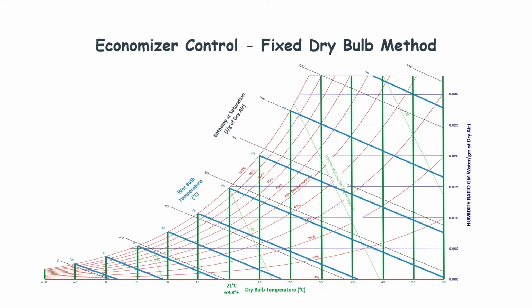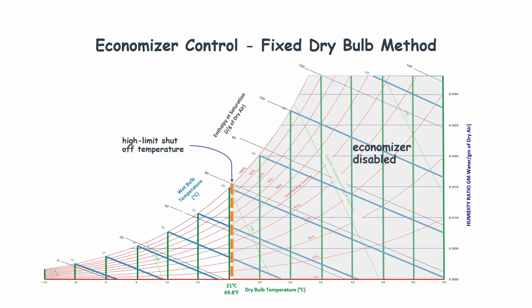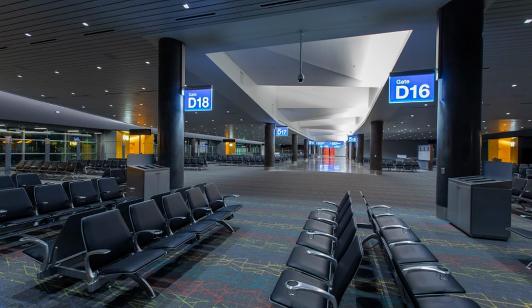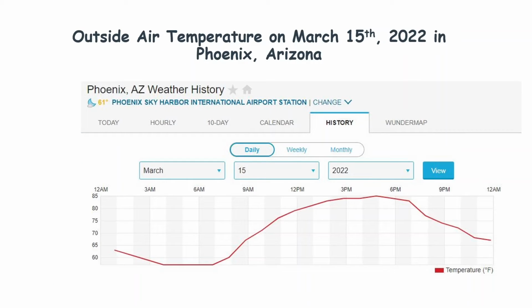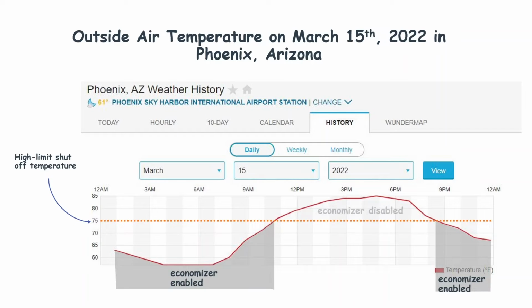The first control method is fixed dry bulb temperature. This is the simplest method. In this method, the controller compares the outside air temperature to a programmed high limit shutoff value. If the outside air temperature is above this high limit, then the controller disables the economizer. Let's look at Phoenix International Airport on March 15th of 2022. If we set the economizer's high limit shutoff temperature to 75 degrees Fahrenheit, then the economizer is active in most of the hours on March 15th. As you can imagine, this saves so much energy for the airport's HVAC system.